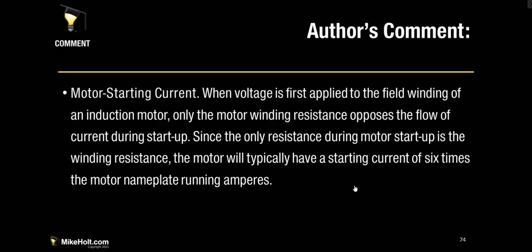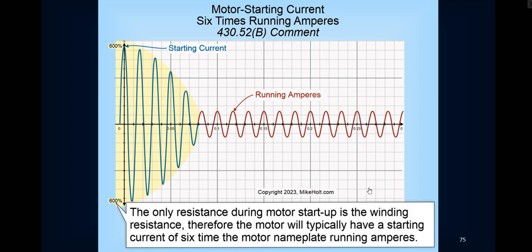Motor starting current. When voltage is first applied to the field winding of an induction motor, only the motor winding resistance opposes the flow of current at startup. Since the only resistance during motor startup is the winding resistance, the motor will typically have a starting current 6 times the motor nameplate running amperes. I'd make a note of that, 6 times, also.